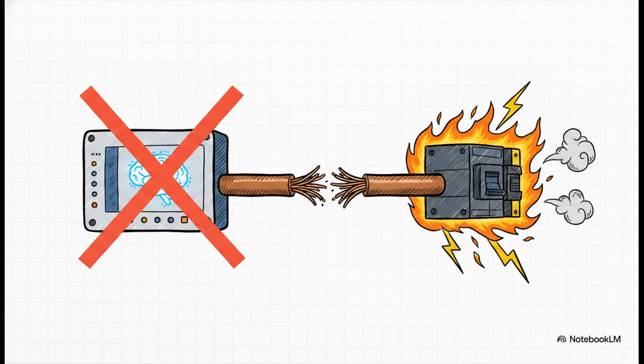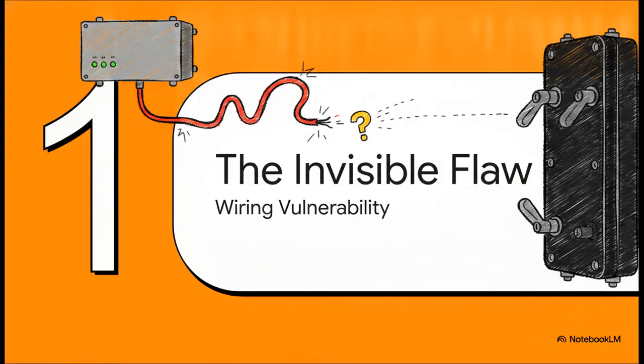Without that physical path, the smartest, most advanced protection relay in the world is completely useless during a real fault. The breaker won't open, the fault isn't cleared, and it just burns indefinitely. All of that incredible digital logic we've built up stopped dead in its tracks by a simple broken wire. Section 1, the invisible wiring vulnerability. Let's get right into it.